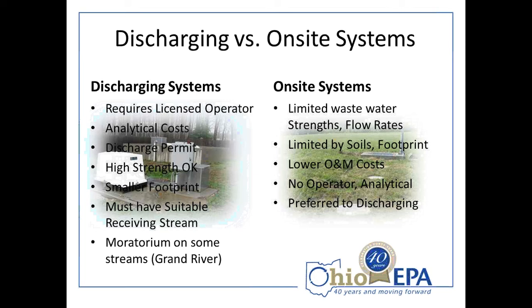For on-site systems, there are limitations on wastewater strength and flow rates — typically systems under 1,000 gallons per day. You are limited by soils and footprint, as soil-based systems can take up considerable space and require appropriate, undisturbed soils. During site development, designate and fence off the area for your system so contractors do not run heavy equipment over it. On-site systems typically have fewer moving parts, lower operation and maintenance costs, do not require an operator, and Ohio EPA prefers on-site systems before considering pipe discharge.